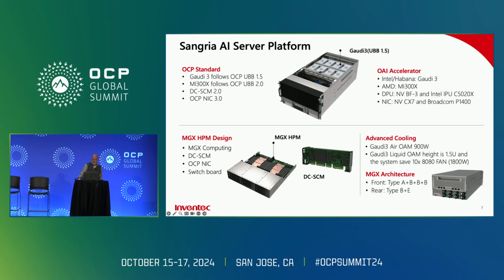The CPU module in this design is an MGX design, but it incorporates DC SCM 2.0 and OCP NICs with a switchboard design. We also, in this design, leverage MGX type A, B, and E for front, rear, and power. And with this, with the liquid cooling version of this, you can save almost 1,800 watts on fans so that your thermal envelope for this can be quite low at 900 watts.